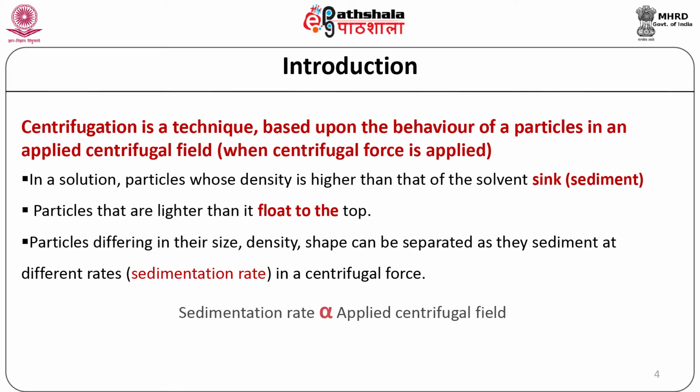The particles are normally suspended in a specific liquid medium held in tubes or bottles which are located in a rotor. The rotor is positioned centrally on the shaft of a centrifuge. Particles differing in their size, density and shape can be separated as they sediment at different rates. Sedimentation rate is directly proportional to the applied centrifugal field.